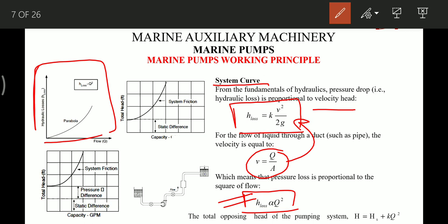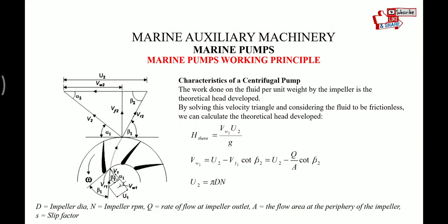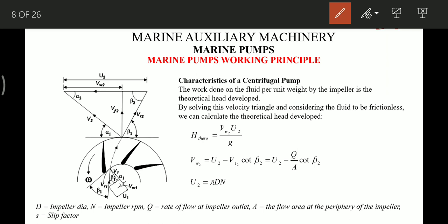The system curve can be of three types: one where there is no static head (fluid flowing in a horizontal plane), one where the system has a static head (curve starts from the static head value), and one where the pump discharges to a pressurized tank (curve starts even higher due to pressure difference). The total opposing head for the pumping system is: H = Hs + k·Q², where Hs is static head plus the pressure difference head.